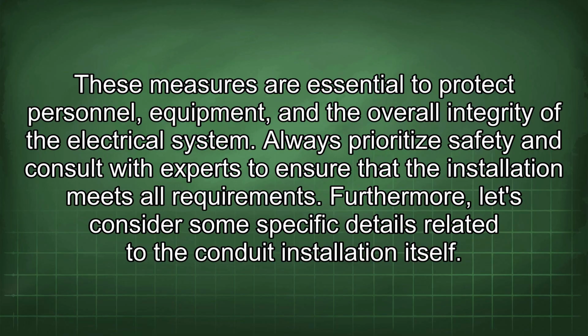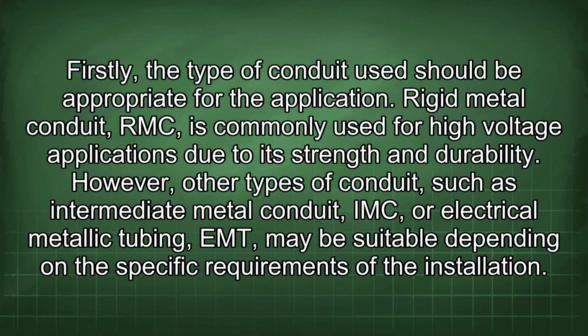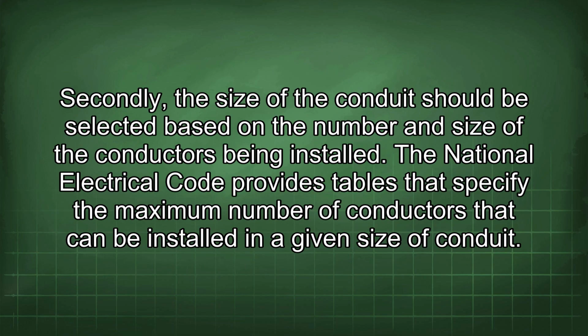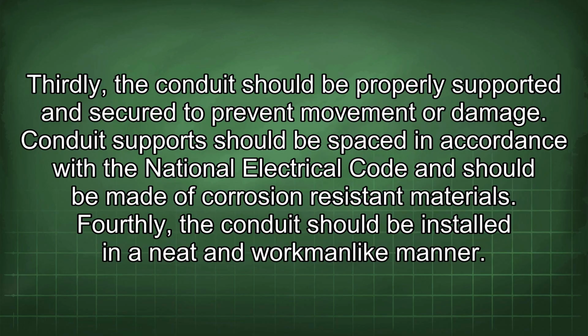Furthermore, let's consider some specific details related to the conduit installation itself. Firstly, the type of conduit used should be appropriate for the application. Rigid metal conduit, RMC, is commonly used for high voltage applications due to its strength and durability. However, other types of conduit, such as intermediate metal conduit, IMC, or electrical metallic tubing, EMT, may be suitable depending on the specific requirements of the installation. Secondly, the size of the conduit should be selected based on the number and size of the conductors being installed. The National Electrical Code provides tables that specify the maximum number of conductors that can be installed in a given size of conduit. Thirdly, the conduit should be properly supported and secured to prevent movement or damage.